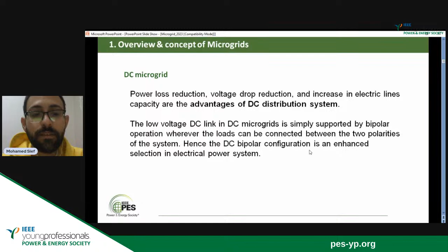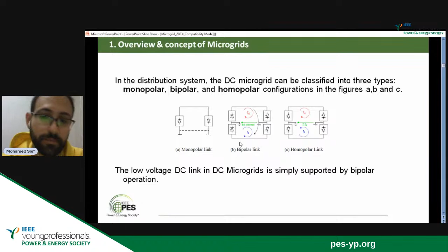As information, the low voltage DC link in the DC microgrid is simply supported by bipolar operation. Bipolar operation enhances the selection of the power system. There are 3 types of connection: monopolar, bipolar, and homopolar. For the DC microgrid we choose bipolar link, which means no current passes between the neutral.